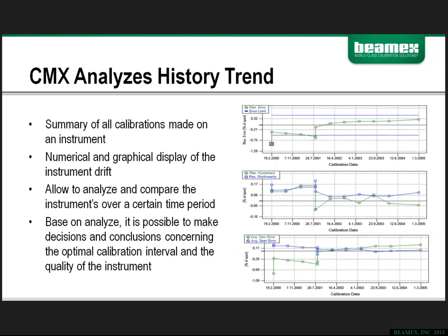So what we've done here is we've blown up the graphical portion of a history trend analysis. And if you look at the bottom row on any of those three graphs, the date format is a little different than what most of us would see here in the U.S. But if you look on the very left, right there, the initial calibration for this device was performed on February 19th of 2000. It was calibrated again in November of 2000, again in July of 2001, et cetera, all the way down through March of 2005.